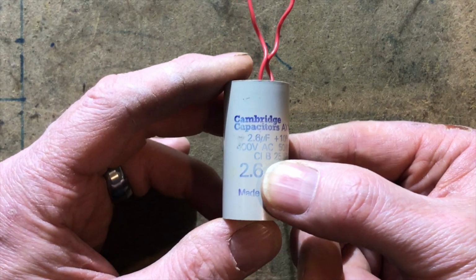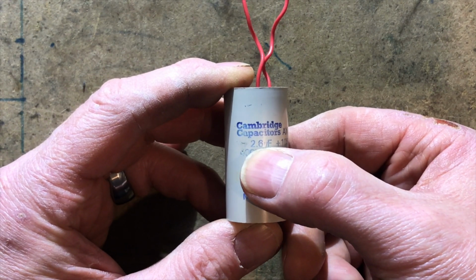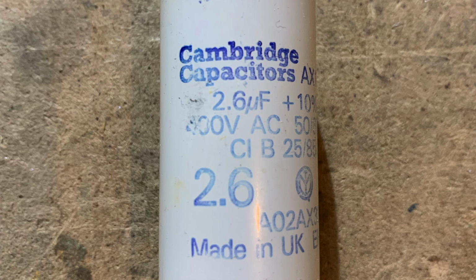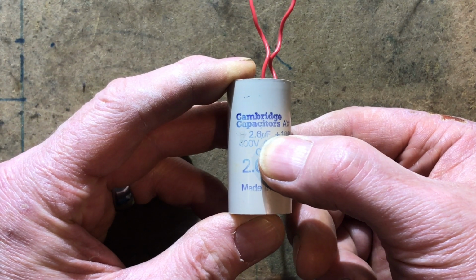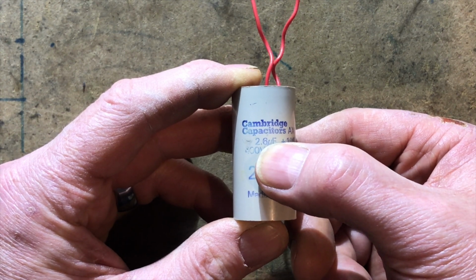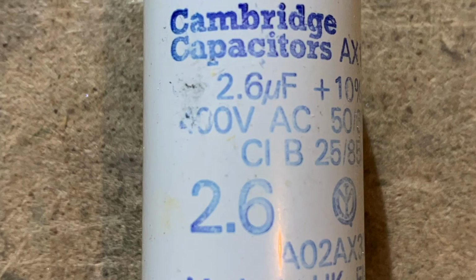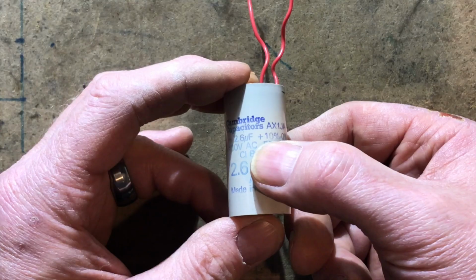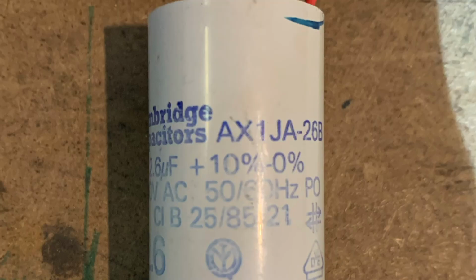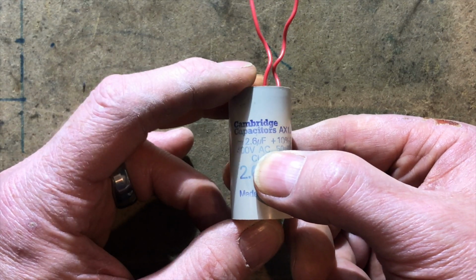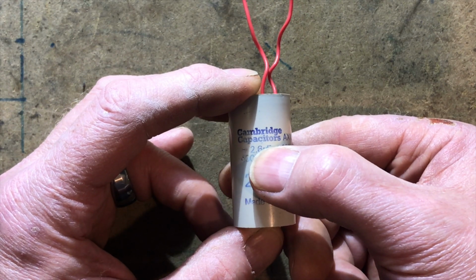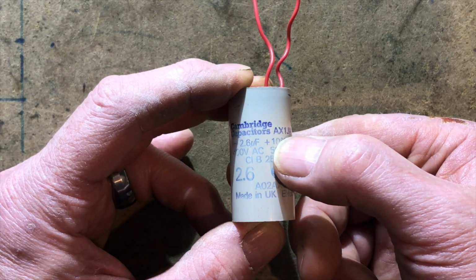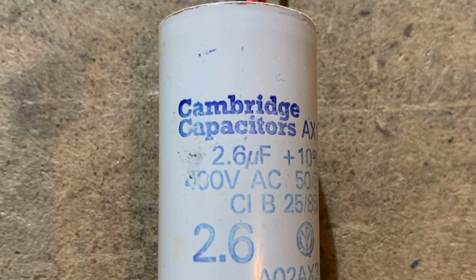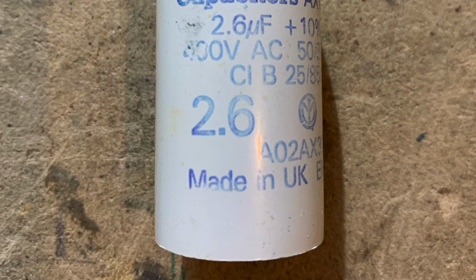So let's have a look at this writing on here. You can see it says 2.6, and then we've got this little U with a tail and an F. That means microfarads. The actual charge in this capacitor is 2.6 microfarad, and you can see it says plus 10% or minus 0%. That's because it's on an AC voltage. It can hold a little bit more than that, not less than that, but it can hold 10% more than that. So you can see it says 400 volts AC, 50 to 60 hertz.